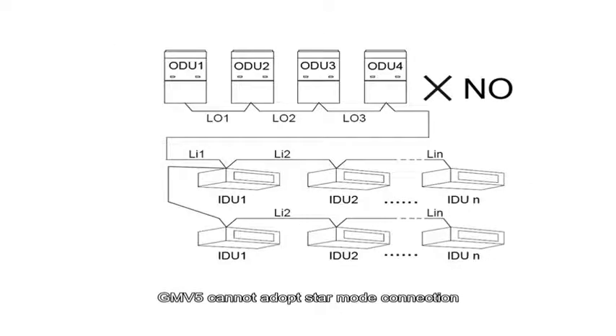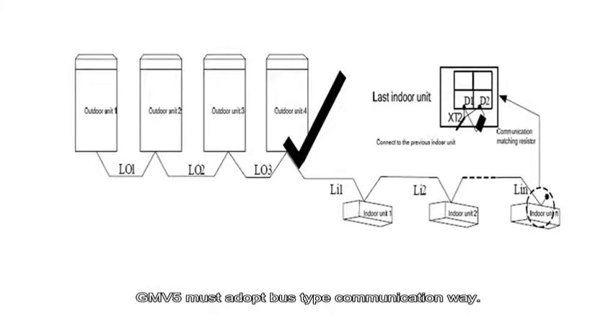GMV5 cannot adopt star mode connection. GMV5 must adopt bus type communication way. The outdoor unit at the beginning of communication shall be set as master outdoor unit. The last indoor unit shall be connected to a communication matching resistor. The resistor is placed in the package of the outdoor unit.